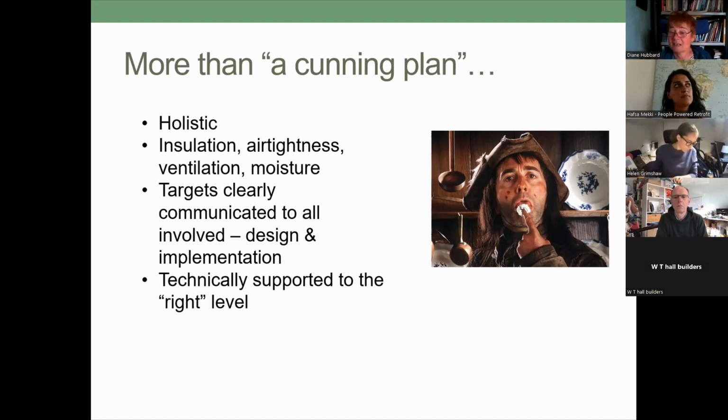The most common thing I come across is people putting quite a lot of insulation into a building and paying no attention to the airtightness of it. The issue this creates is that you can spend quite a lot on insulation, but the performance of the insulation is affected by air moving through it or around it: thermal bypass.